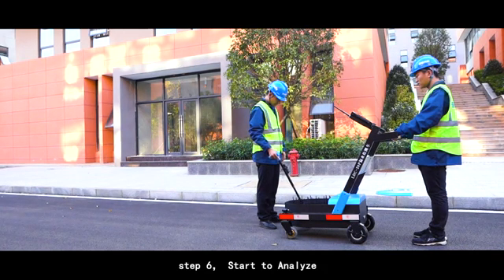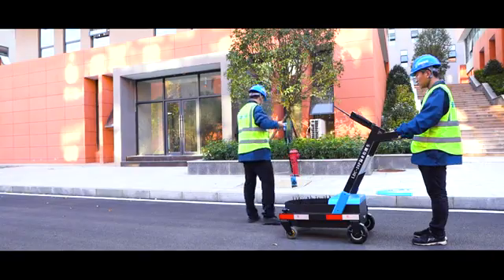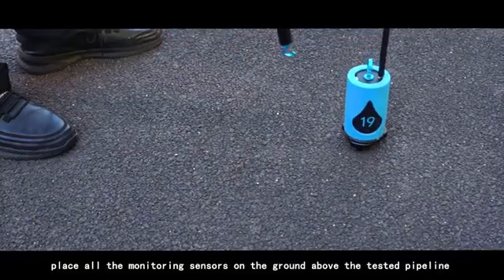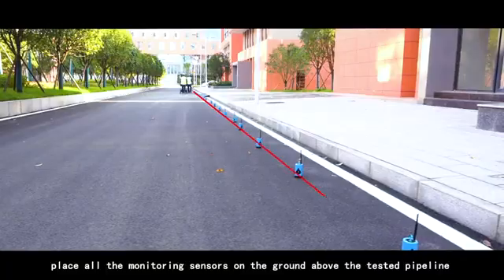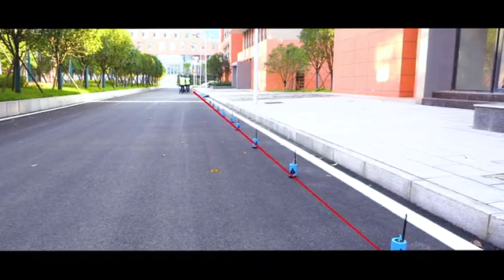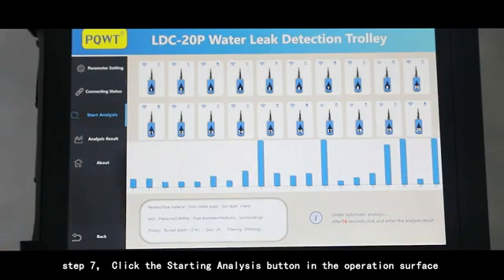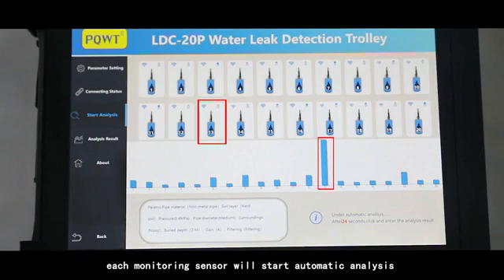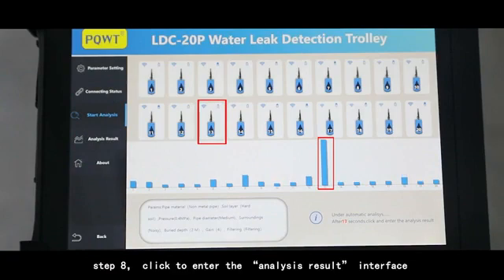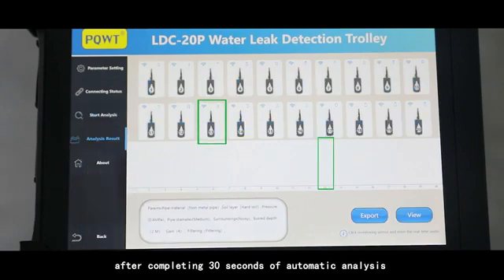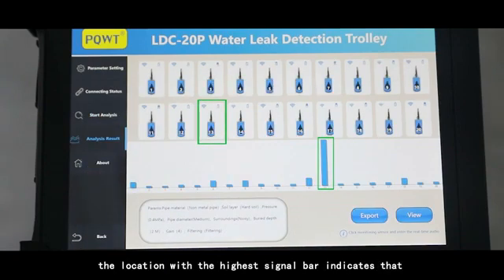Step 6: Start to analyze. Place all the monitoring sensors on the ground above the tested pipeline. Step 7: Click the starting analysis button in the operation interface. Each monitoring sensor will start automatic analysis. Step 8: Click to enter the analysis result interface after completing 30 seconds of automatic analysis.